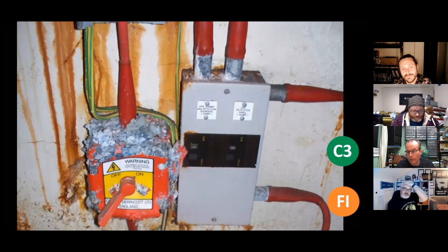John, your view on it? Yeah, I mean, C2, I mean, it's not dangerous. Like, there's not live bits hanging out. It's not good, but so C2 would be... it's not good, but... Yeah. Dan? I want to know more. I know you do, but come on, code. I'm going to say a C2 from a 7671 perspective. Dave? Yeah, C2, but maybe C1 if the fire alarm does not work as it should.